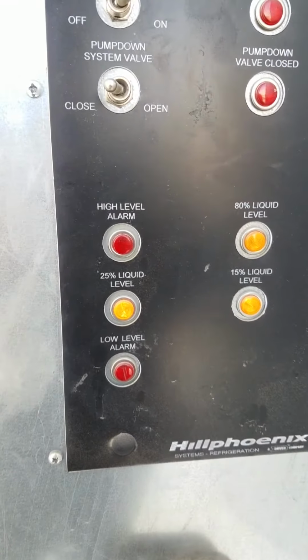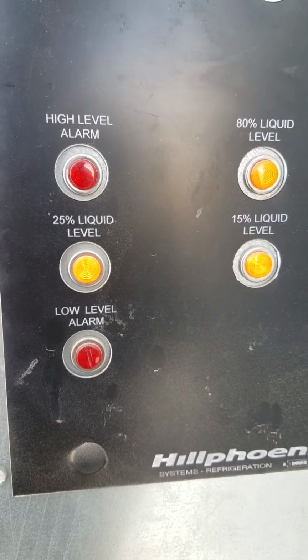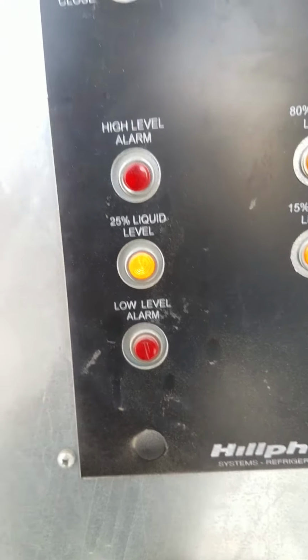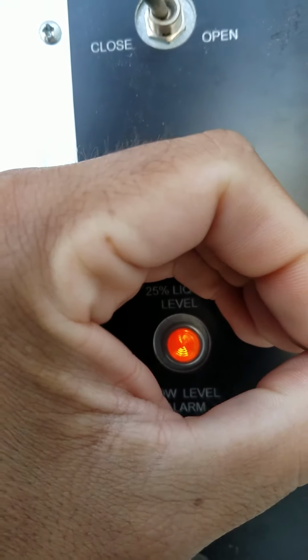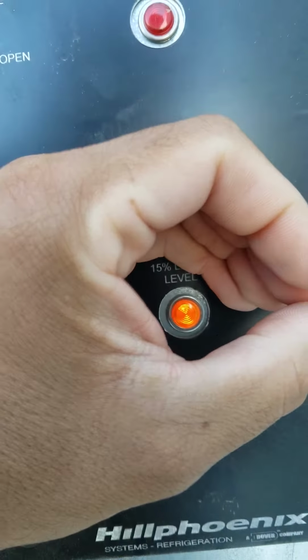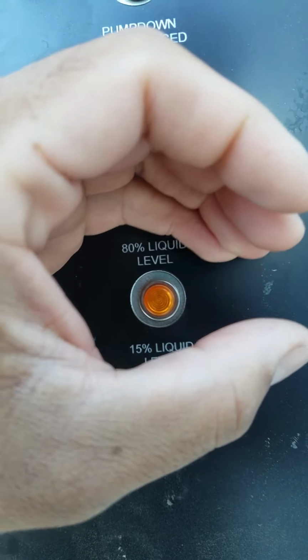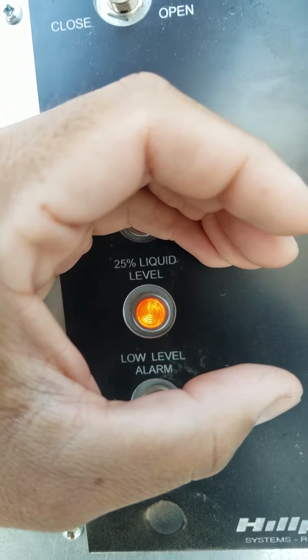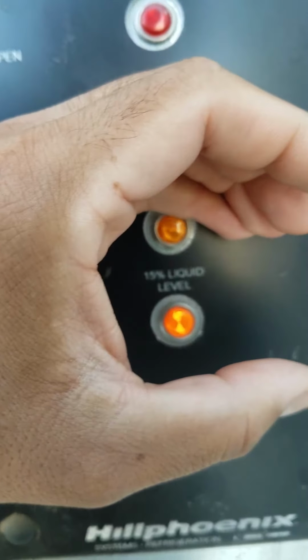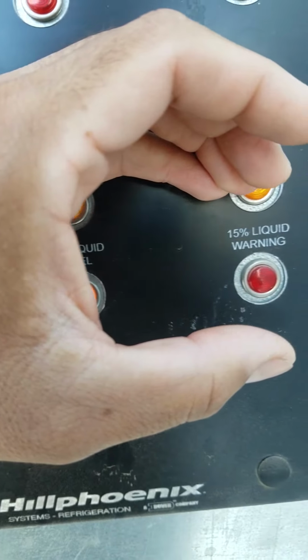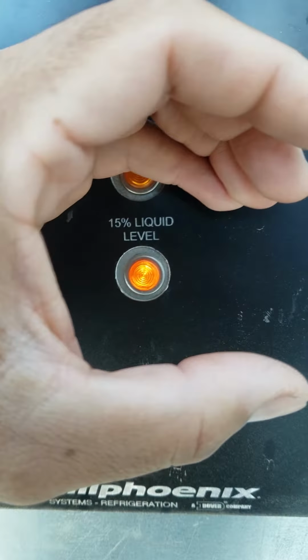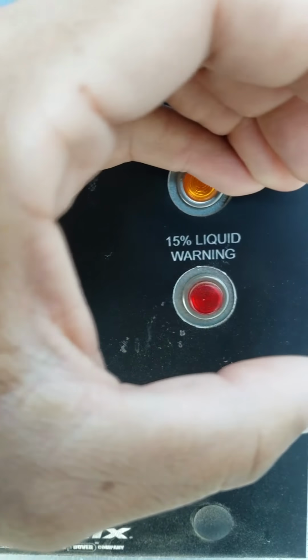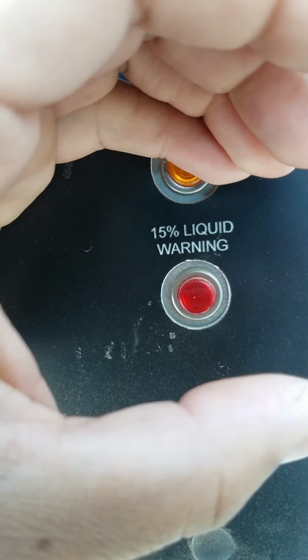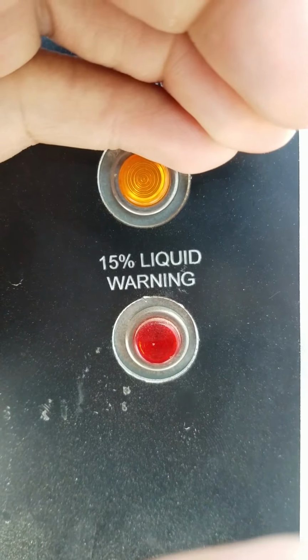Then back over here on the pump panel, you got your liquid level at 25%. It's illuminated right there. 15% is illuminated. It'll keep illuminating all the way up. See how this one's not? That's 80, that's 50, and 25 is where we need to be. When it gets a little bit below 15, see how it says 15% liquid level, amber light, then you got 15% liquid warning, red light. So when it goes below, it starts alarming red.